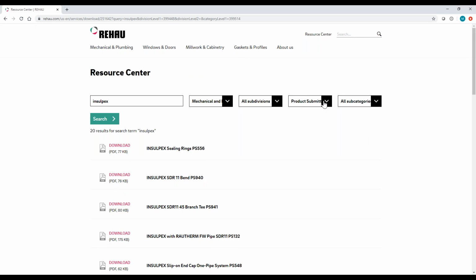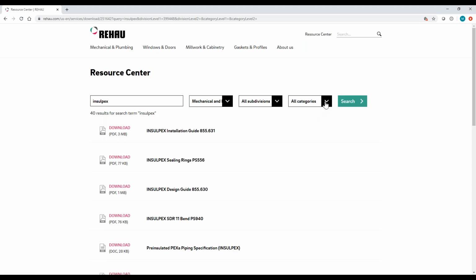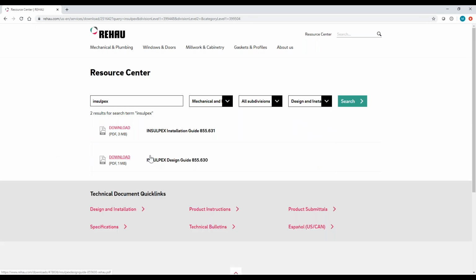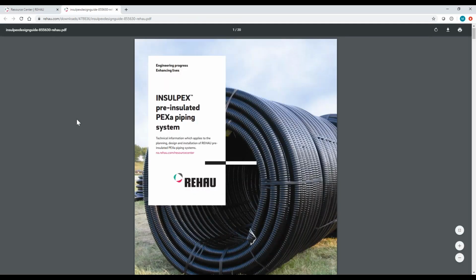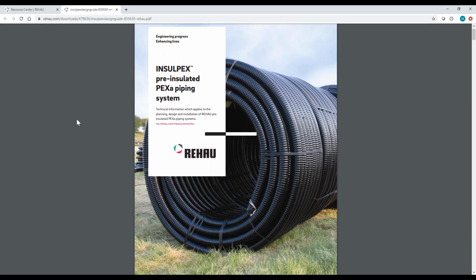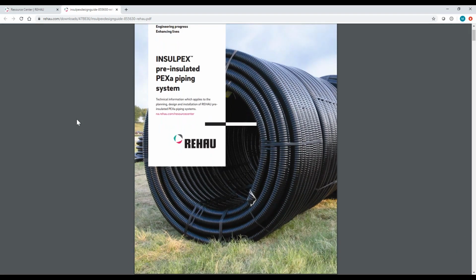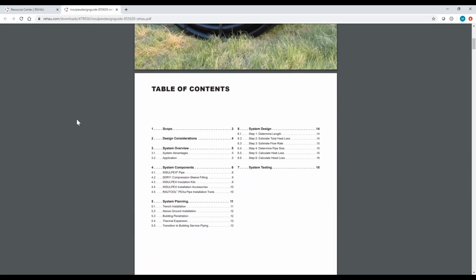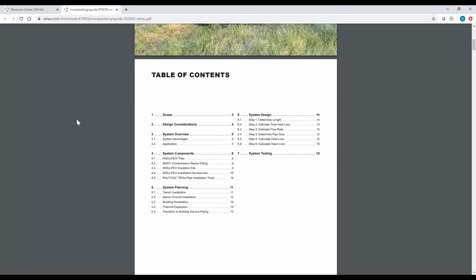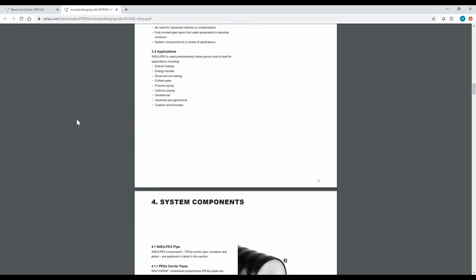For some round numbers, it's 132 PSI at ambient, so 132 at roughly 73 degrees Fahrenheit, and that's on the high end. The other end of the spectrum is 58 PSI at 200 F. These are considered low temp hydronic systems, with 200 being our cap. We try to design these systems at a happy medium of 180 degrees for the fluid temperature, and at that point the pressure is 66 PSI, 180 degrees Fahrenheit at 66 PSI going hand in hand.